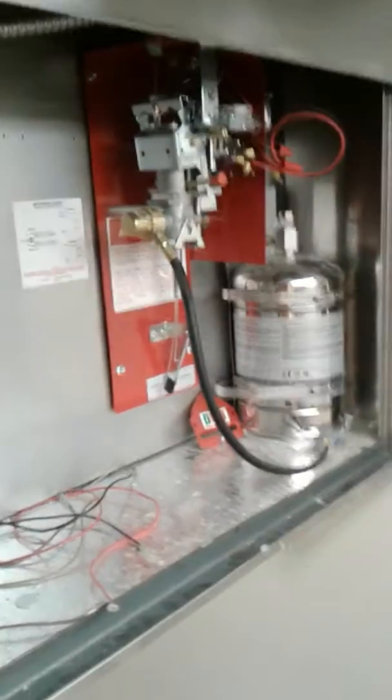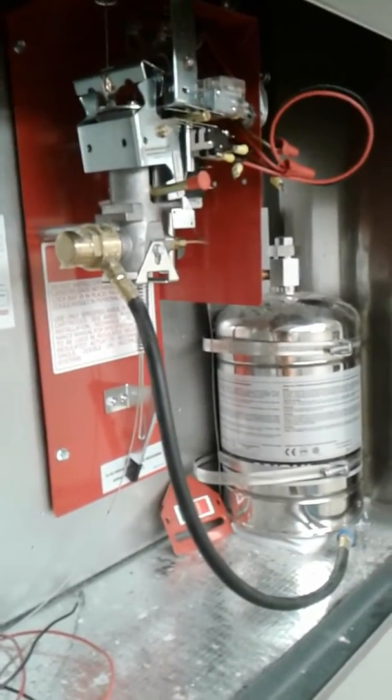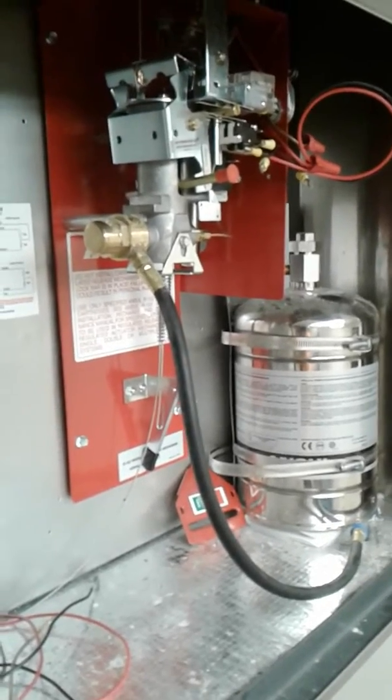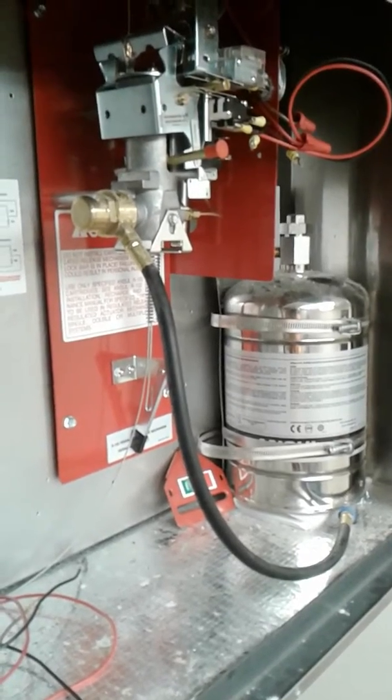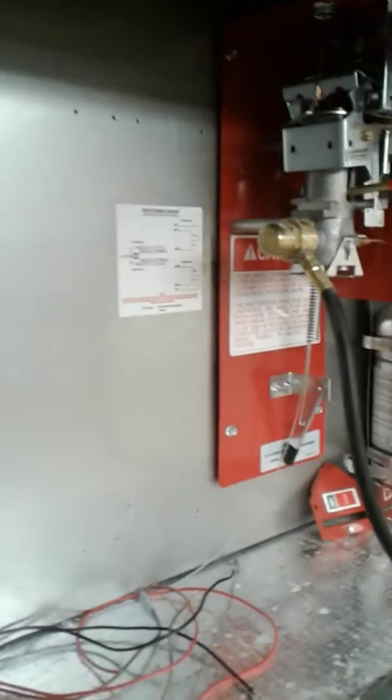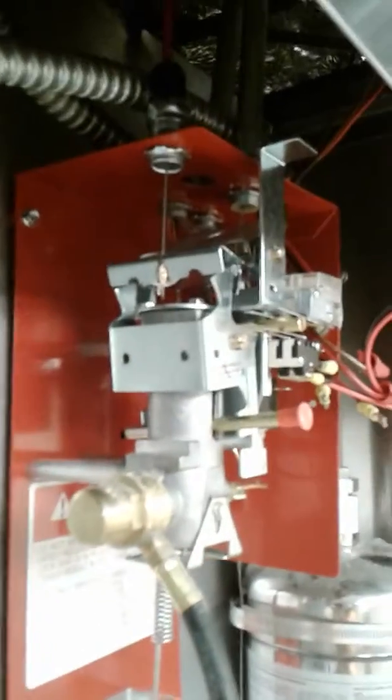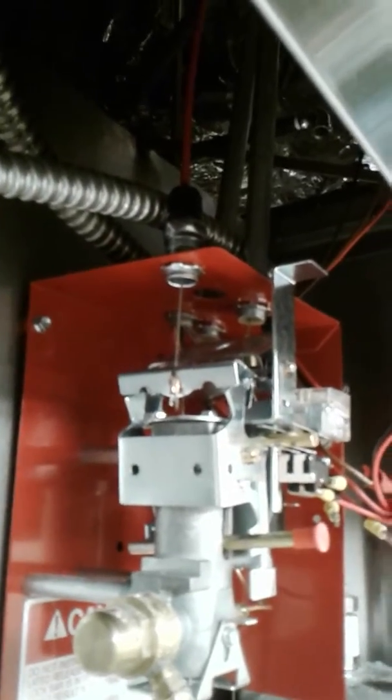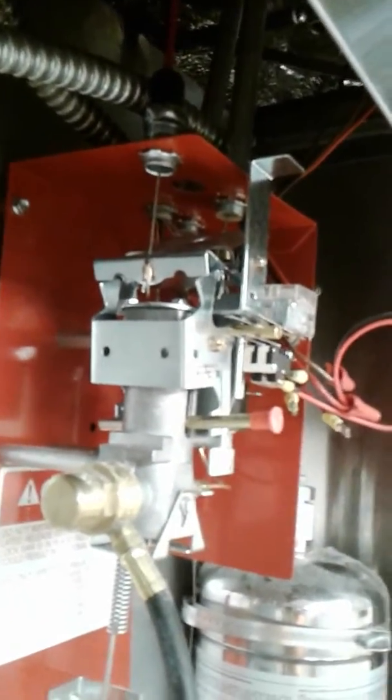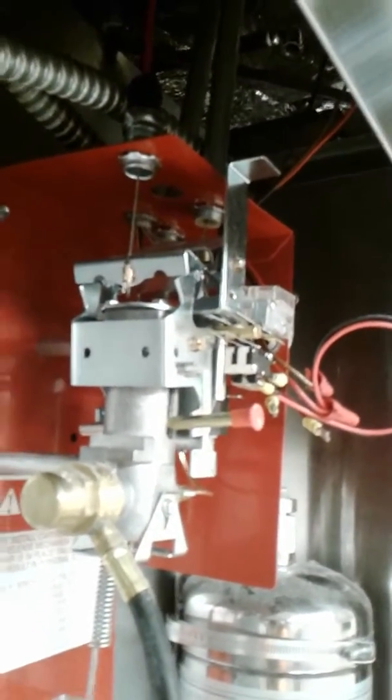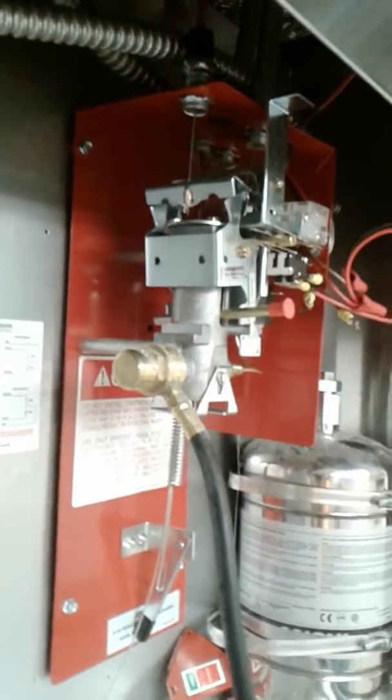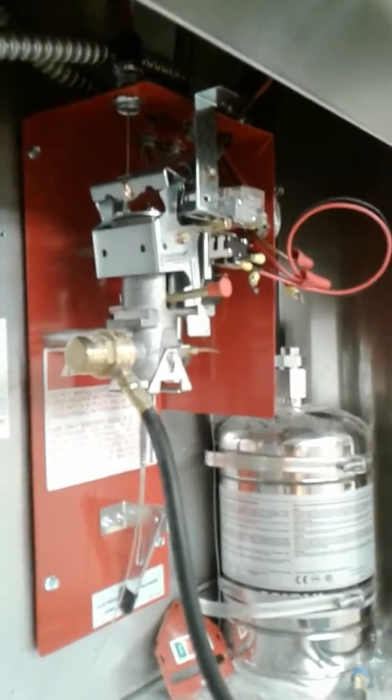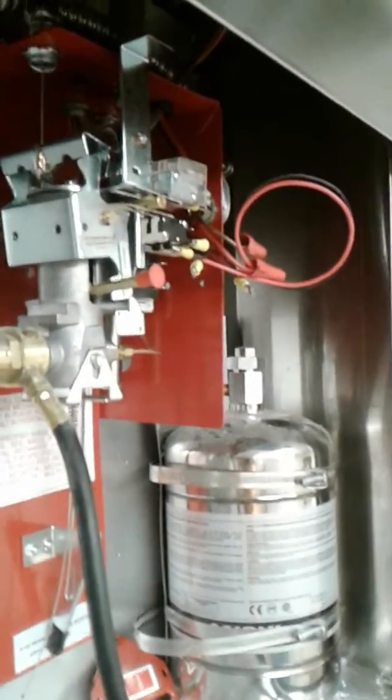Now you can see, over here, this system's been set off. Earlier there was some data guys that were in here working and installing a TV, an instructional monitor. And you can see that cable right there. It's got that red cable coming out of the top of it. It hooks right there to the system. There's another one over there from pull station. The cable that connects into it. The cable got pulled. This system got set off. Fire alarm went. It wasn't good.